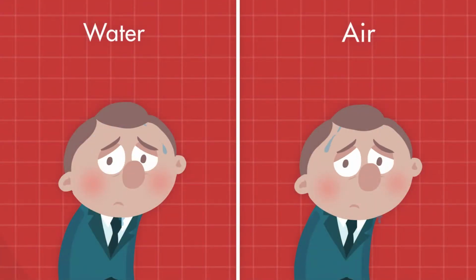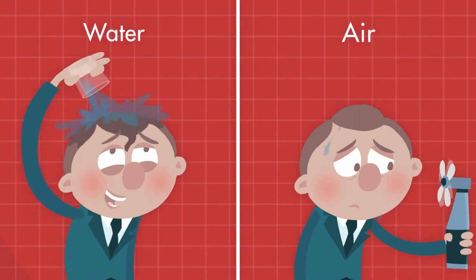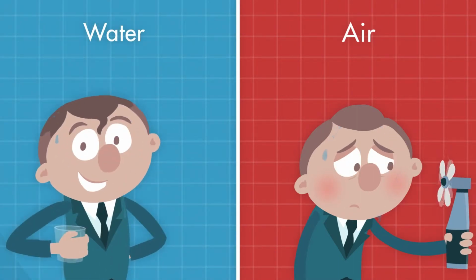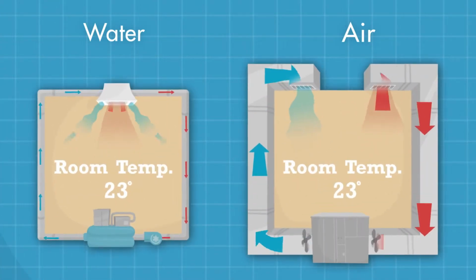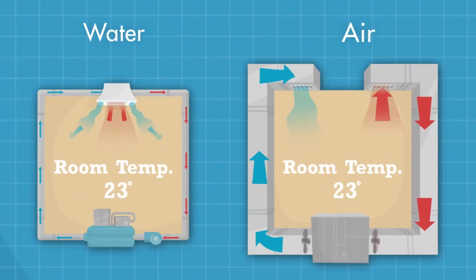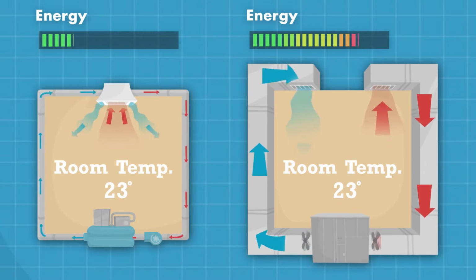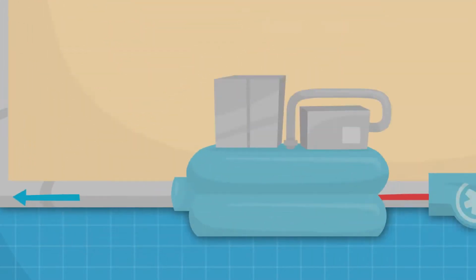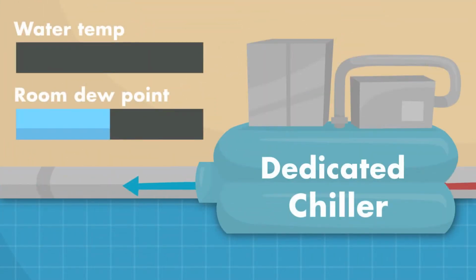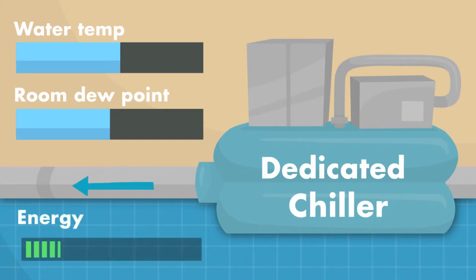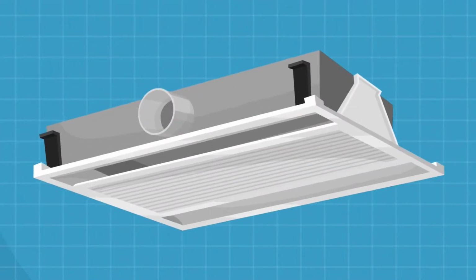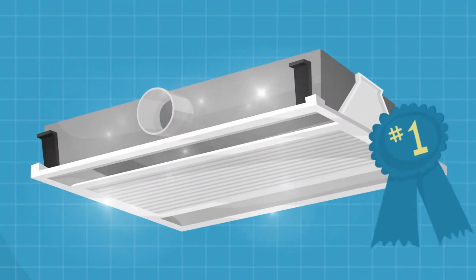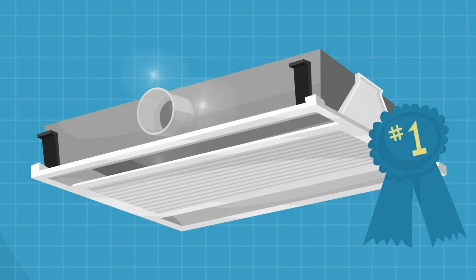First, there's efficiency. Active beams rely on the superior heat transfer properties of water versus air, meaning you only need to circulate small volumes of water to do the same amount of cooling as air, saving energy along the way. Meanwhile, to effectively cool a space, the water circulating through the coil need only be chilled to a temperature just above the room dew point. That means the dedicated chiller uses less energy to deliver the same cooling. When you add up all these savings, it's easy to see why active beams are so efficient.